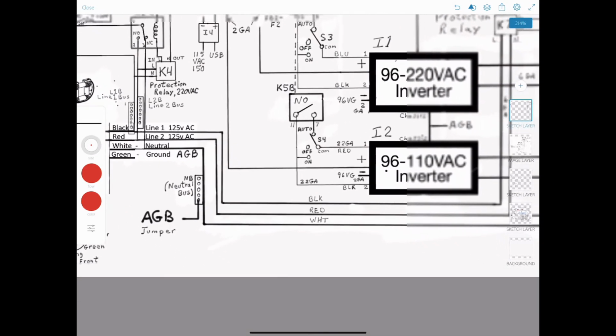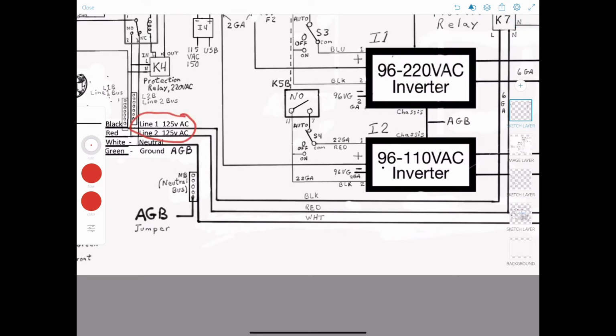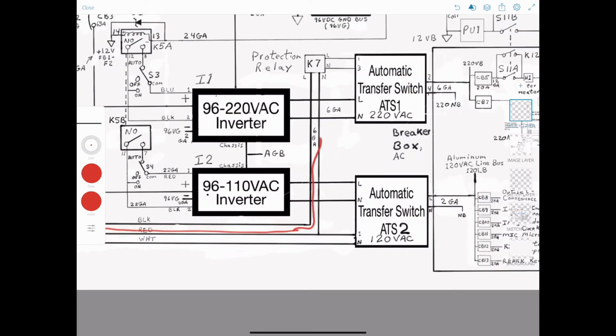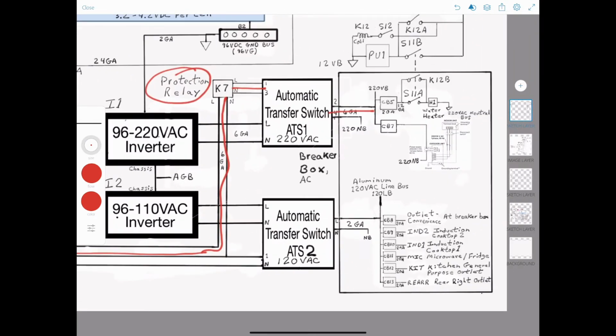Second thing I'm going to show you, coming over here to the breakers. Each one has a 50 amp breaker, hence the 50 amp shore power, and those are ganged breakers, so they work together. And then they're split up into two, I call it 125 VAC, volts AC legs there. I kind of use that interchangeably with 120. They both go over to what they call a protection relay. So both legs go in there, and the protection relay delays, checks the power, makes sure the voltage is right and the frequency is right. And if it's okay, it goes into the automatic transfer switch, which then transfers it to the loads, which includes the mini split system here, or my true instant hot water system. So that's the only requirement I have for 220.